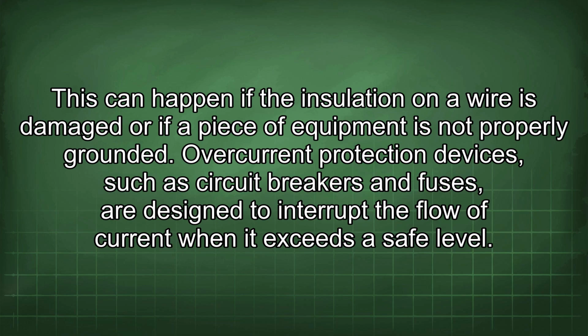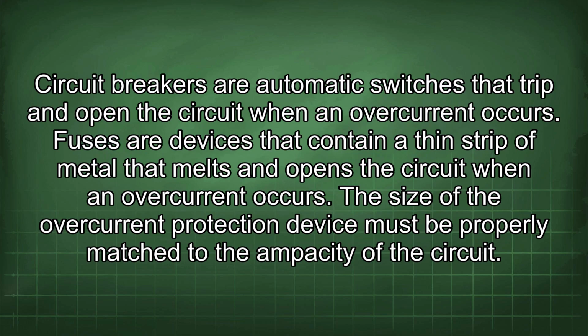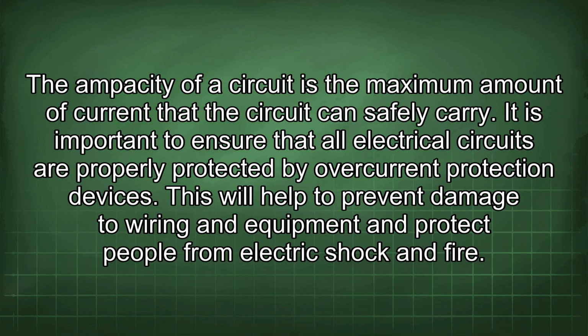Overcurrent protection devices, such as circuit breakers and fuses, are designed to interrupt the flow of current when it exceeds a safe level. Circuit breakers are automatic switches that trip and open the circuit when an overcurrent occurs. Fuses are devices that contain a thin strip of metal that melts and opens the circuit when an overcurrent occurs. The size of the overcurrent protection device must be properly matched to the ampacity of the circuit. The ampacity of a circuit is the maximum amount of current that the circuit can safely carry.